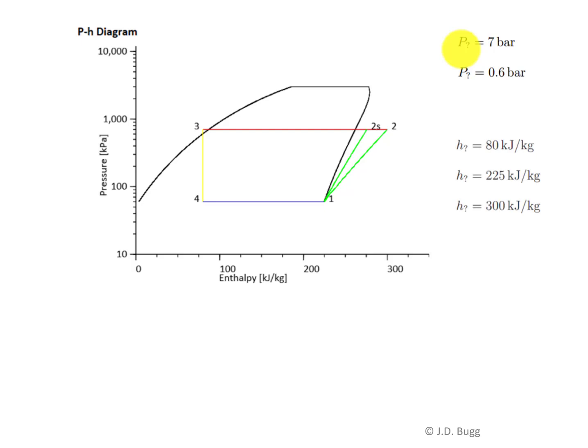Likewise, the three enthalpies, we can figure out where those are as well. Notice point 2s is not a real point, that's a hypothetical or an ideal exit. So they would not have measured an enthalpy at that point. So there only are three enthalpies. We dropped down from this point, that has to be the maximum enthalpy. So H2 has to be 300. The intermediate one here at point 1 has to be the in-between value 225. And the enthalpy of points 3 and 4 are equal, and they have to be the lowest enthalpy in the cycle, or 80 kilojoules per kilogram. So our knowledge of the pH diagram tells us where all of these were, even though it wasn't recorded in the logbook.